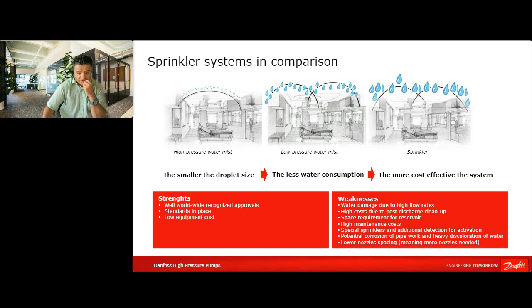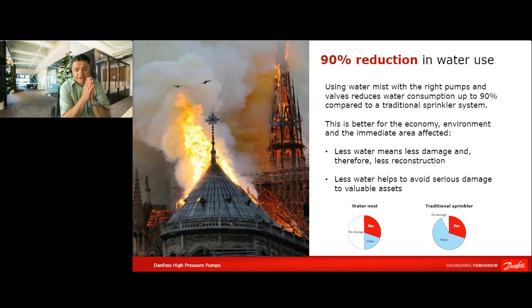Then there is also the risk of corrosion inside the pipes, because they are not using stainless steel pipes, which is the case in the high pressure water mist system. So in a high pressure water mist system, all the parts in touch with water are made out of stainless steel or corrosion-free materials, which is also a big advantage. I have spoken about the water damage. It is clear that a fire hazard which can be extinguished with less water is environmentally more friendly. It is money saving after the fire incident, and it needs less water reserves, smaller water tanks, saving money on that side.